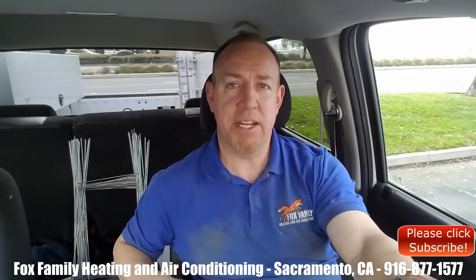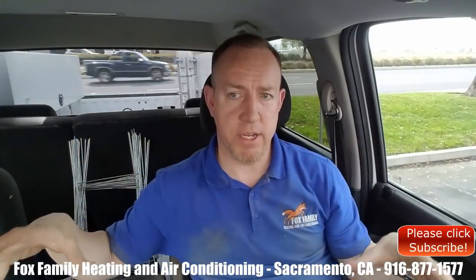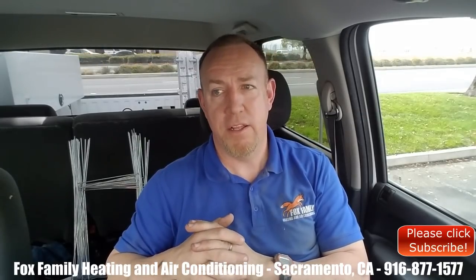I'm under the house, took a couple pictures, and looking at it I'm thinking that's going to be like a $3,000 or $4,000 job, and you've only got one 16-inch duct supplying that — that's like 1,000 CFMs feeding the trunk for the whole house on this 5-ton system. So I said, why don't we abandon what you guys have going on down there, and we'll put all new ductwork up in the attic, cut in all new registers in the ceiling, and run our ductwork out from there.